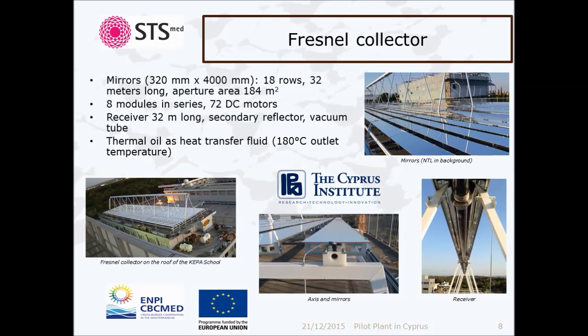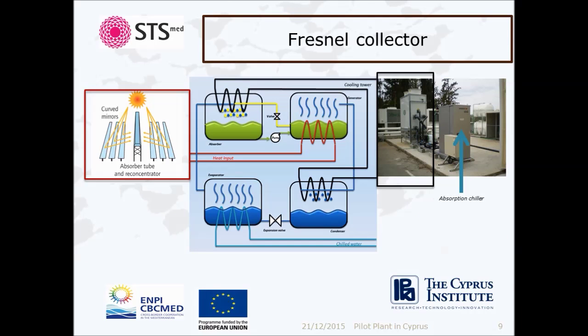The 32 meters long receiver encloses a secondary reflector which concentrates the solar beams from the mirrors around the pipe. The receiver also encloses a vacuum pipe through which circulates thermal oil reaching 180 degrees at the outlet. The heat produced fires an absorption chiller which provides cooling to the building thanks to heat. The absorption chiller installed for the NTL is a lithium bromide chiller with a cooling capacity of 35 kilowatts, and its coefficient of performance is 0.7.